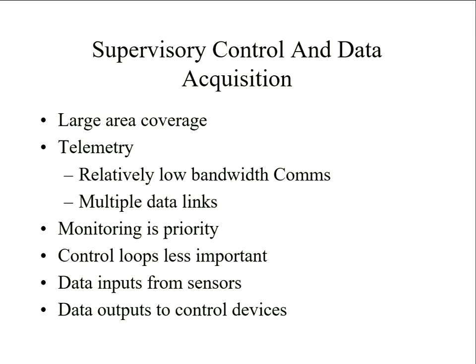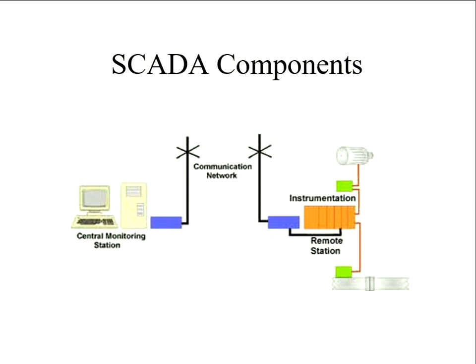The intention was to really try and have the same mimics on site as the control room have, because often the key confusion is I'm going on site to maintain slam shut A, and I could only see slam shut 1 and slam shut 2 on my screen. So if you don't have the same understanding of what's on site, it makes maintenance more complicated. So having the same diagrams and looking at essentially the same data is a relatively recent aspiration, because in the end you're not trying to replicate a control room at site level, because you've probably just got a small kiosk with a bit of equipment there.